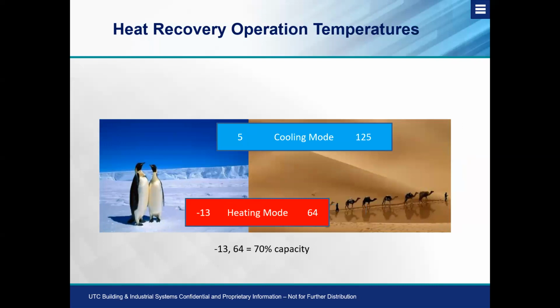Now, on the heat recovery side of things, we look at the cooling mode as being able to go down to 5 degrees all the way up to 125 degrees. And at 5 degrees in the cooling mode, we're going to give you 70% of that rated capacity. And in heating mode, we're rated down to -13 all the way up to 64 degrees. And at that -13, we are also going to give you 70% of that unit's rated capacity at -13.